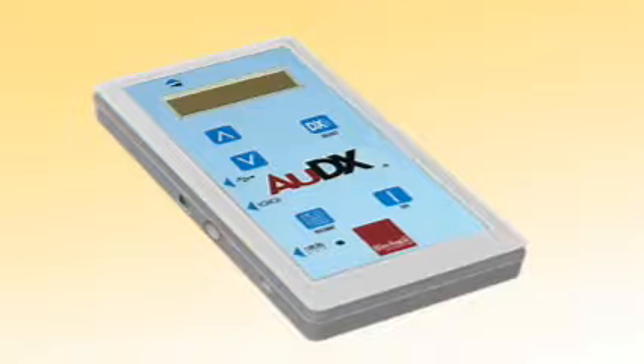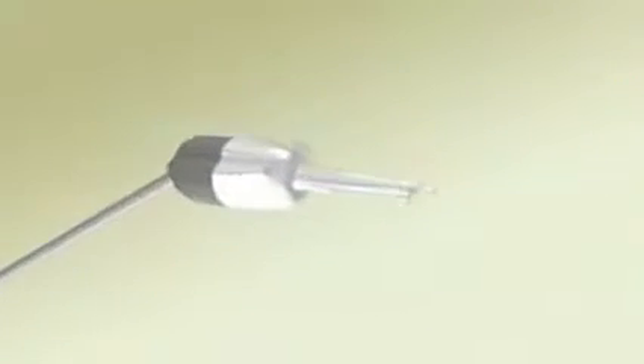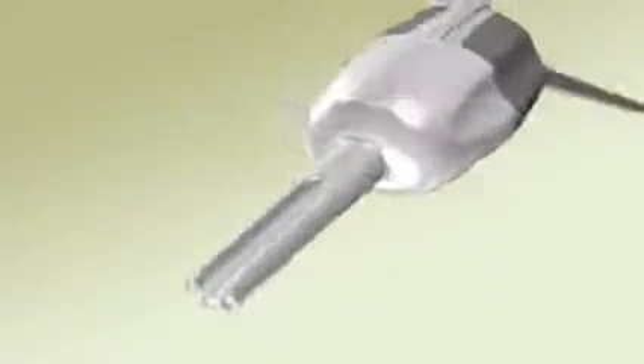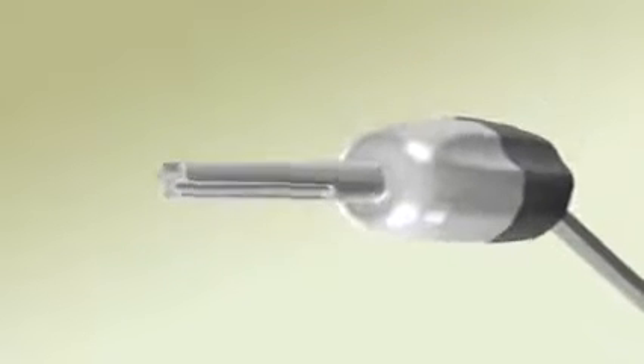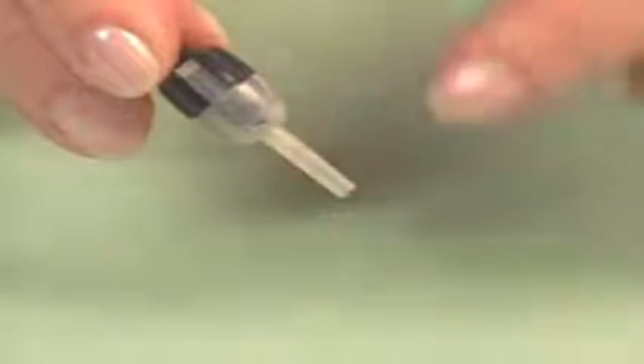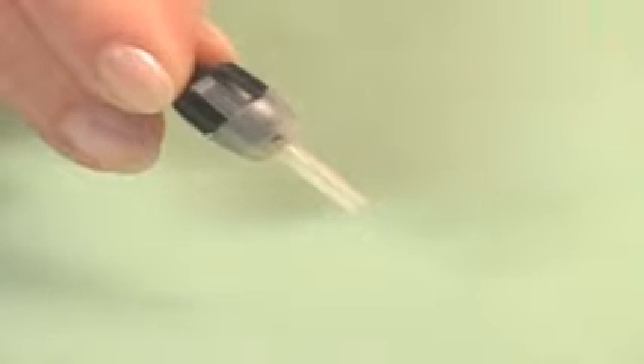Proper maintenance of the AuDX system will make testing more efficient and extend the life of the equipment. Inspect the probe nozzle for debris in any of the 3 grooves. If debris is present, clean the grooves with a tissue or gauze pad. An alcohol wipe can also be used. Be sure to clean the grooves from the base to the tip to avoid allowing any liquid or debris to move into the closed channels at the base of the grooves. These closed channels cannot be cleaned, and the nozzle will need to be replaced if they become clogged.